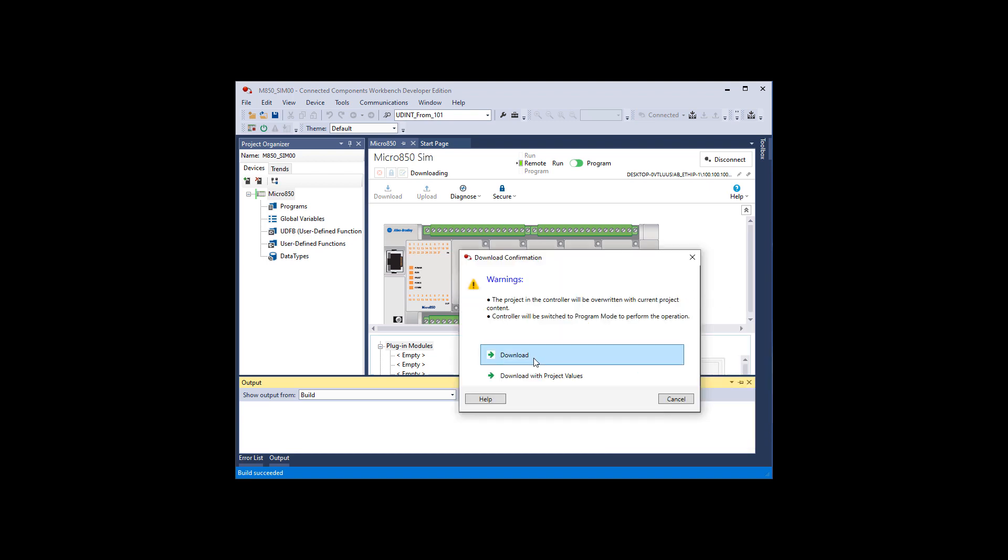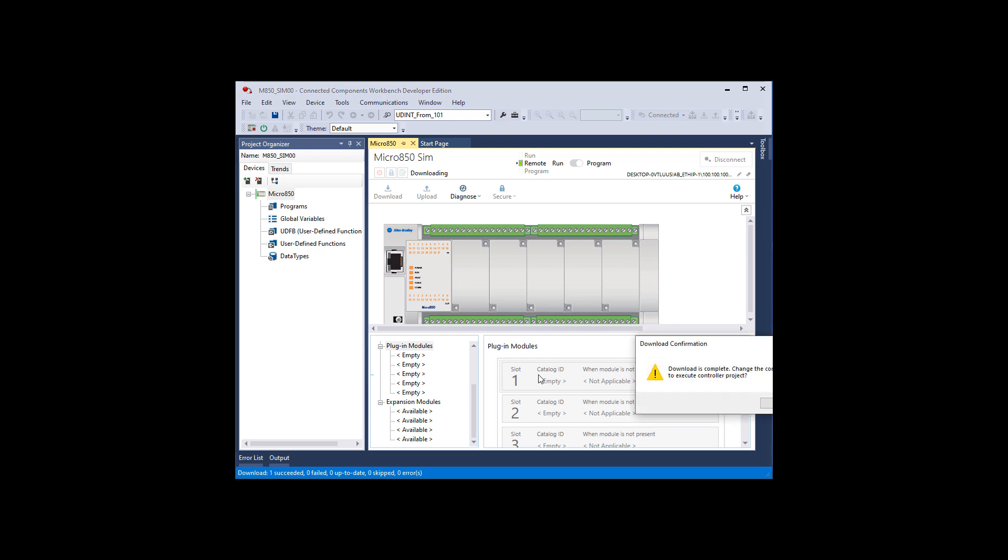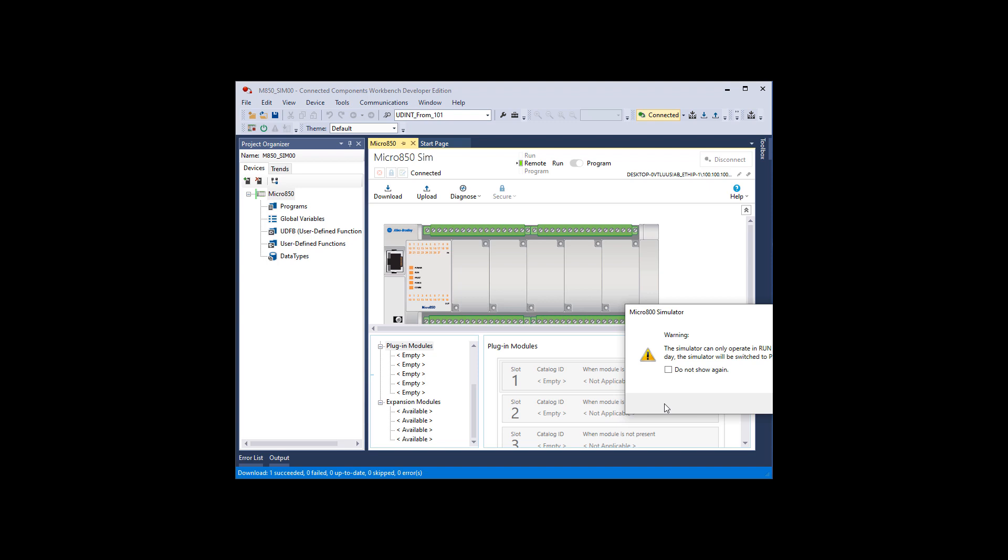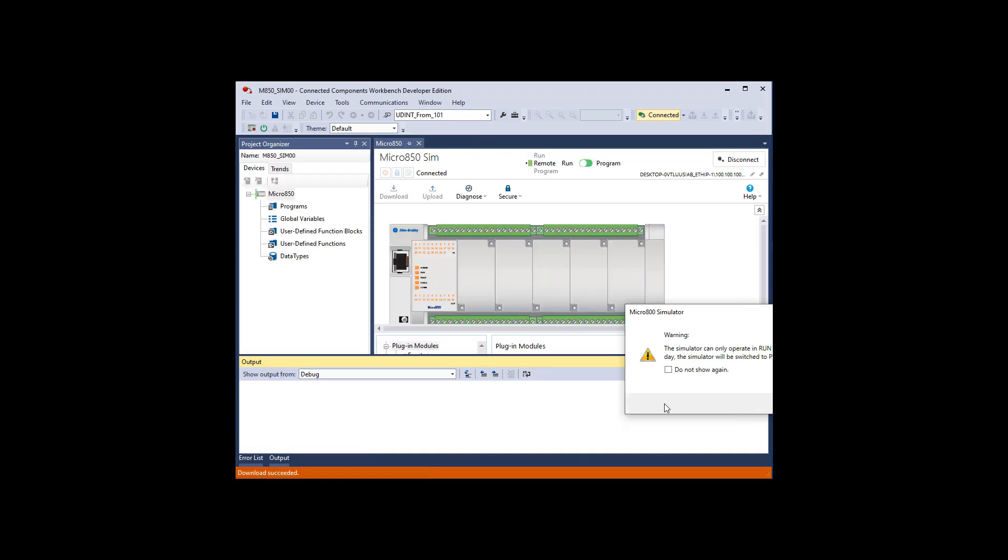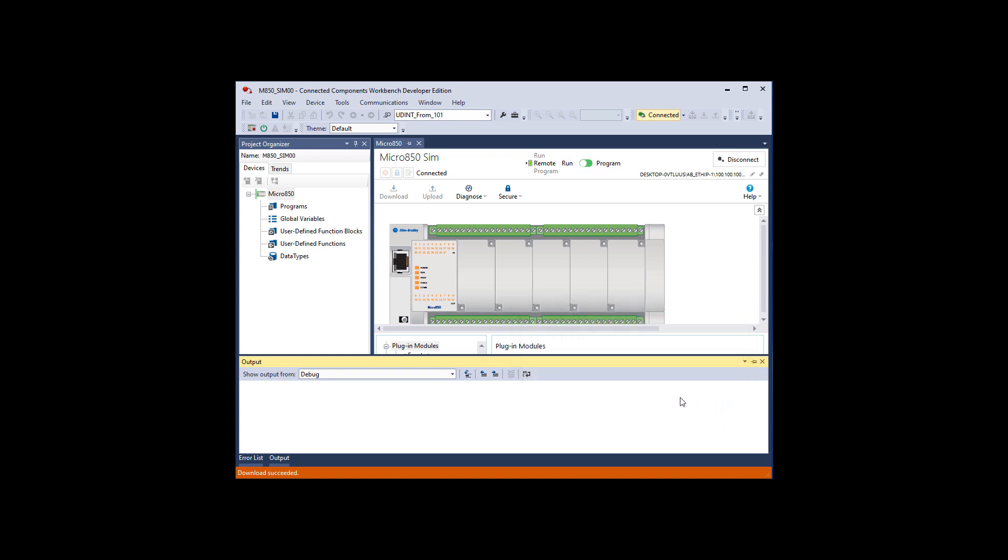If you download, if you download it's only going to download the programs, not the project values. We want to download the project values. And I would advise you, while you're doing this training course, you're using the manuals and doing projects, I would always download with values. Because if you don't, then what you did offline, if you entered any values as far as configurations, they're not going to get downloaded. And you're still going to have online what you had when you left and went offline to make edits. So if you make edits offline, and it includes any data, timer presets, values, and registers, anything, that won't download unless you pick download with values. Here's our message again. You'll get tired of seeing that. Okay, now we have a program in, well, we don't have a program because I didn't create any, but we have a project downloaded, so we have an empty program.